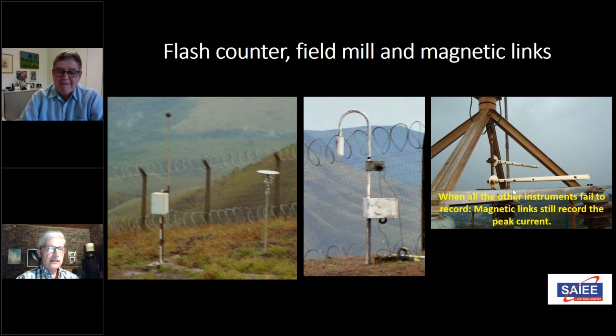Let me talk about the bottom of the tower a little bit. These funny white tubes you see there were a project Andrew delegated to me. I had to calibrate these things. For those who don't know what you're looking at, you see these little black dots—they're what we call magnetic links. It's little tubes with essentially a hard magnetic material inside, so that if a lightning strike current goes down the center conductor, the magnetic field generated leaves remnants in those links, proportional to the peak of the current that came down the conductor.